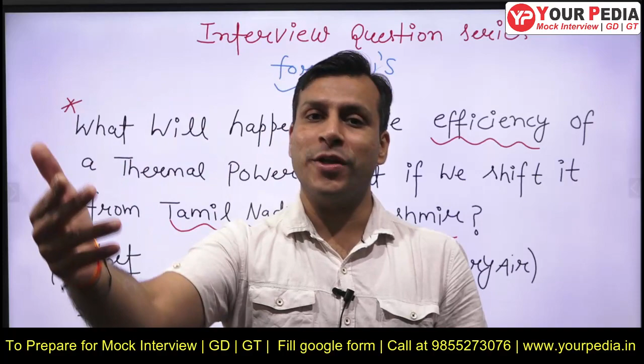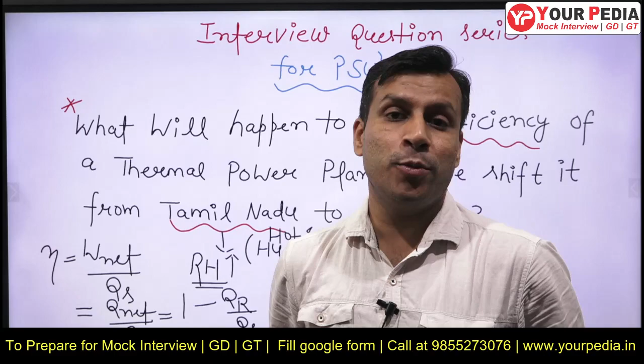But here, when you are shifting it from Tamil Nadu to Kashmir, in Kashmir we will be able to carry out effective condensation, so heat transfer is going to increase, and we will be able to achieve a very low condenser pressure. So the condenser pressure will be low, and the pressure difference between the inlet pressure at the turbine and the exit pressure will be more, and the work output will increase. The closed area in the Rankine cycle also increases, because we will be able to maintain a lower condenser pressure.